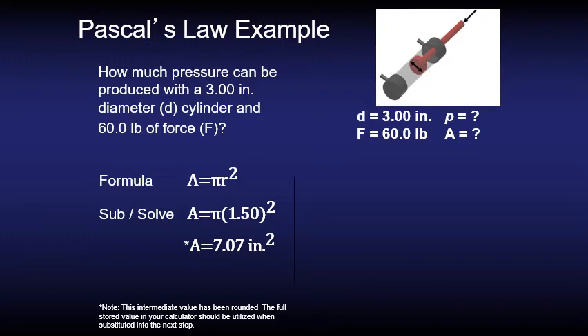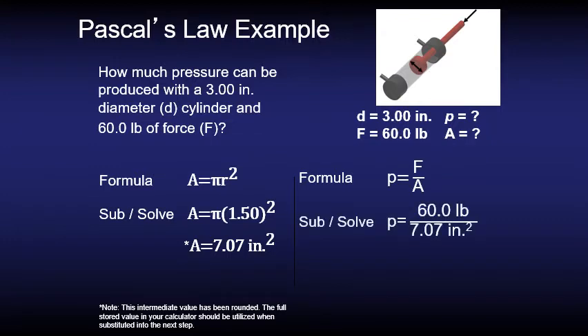So let's put that into the Pascal's law formula. Pressure is force over area. When we put those numbers in, the 60 pounds of force and the 7.07 inches squared of area, we get a pressure of 8.49 pounds per inch squared.